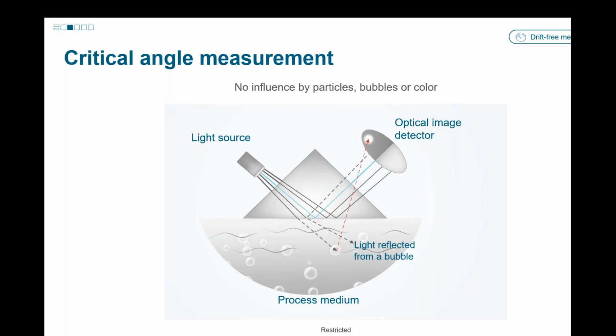It's very robust. I don't think I actually get into the core optics, but it's a very stable potted thing. And think of it as a pair of binoculars. You really don't have to calibrate a pair of binoculars or an electronic camera. They're very stable inherently. Same thing here, it's potted in epoxy and nothing really changes. The only thing that could change is that prism, if it gets scratched and damaged and needs to be changed out, you would send it into our factory and we would do that calibration for you.